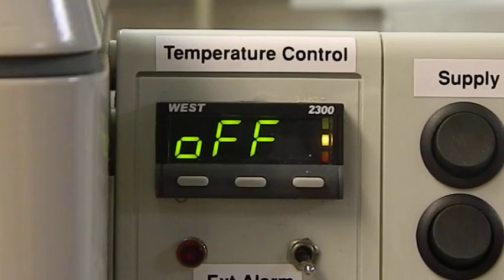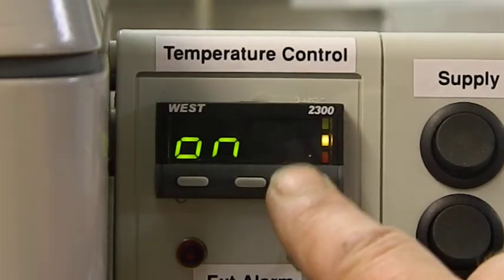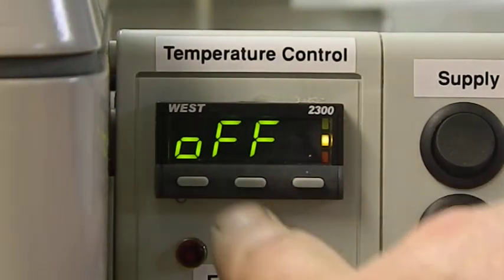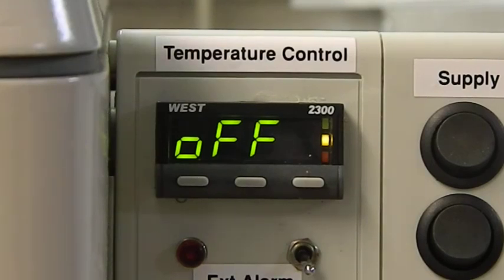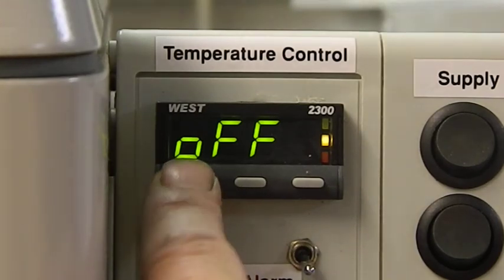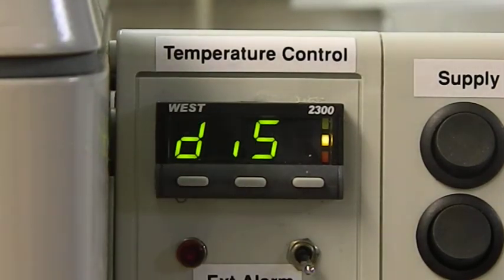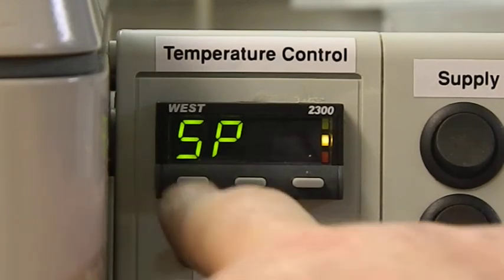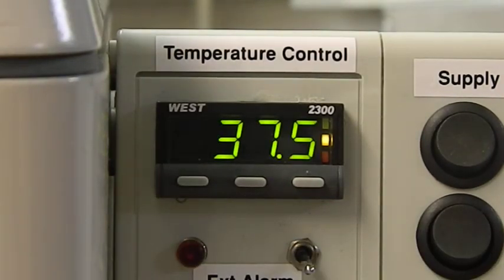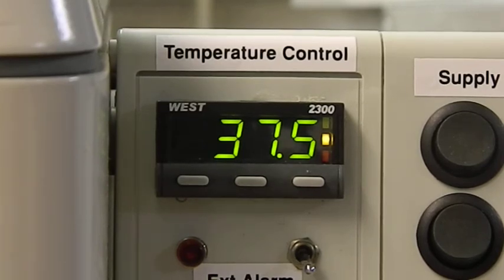SPL, this is a set point lock. If you don't want anyone to be able to change the settings you put in, you change this to on, and it'll lock out the buttons. So without going back into the parameters, it stops little fingers changing things. But again, we leave that off as a default setting. AEN, this is in disable mode at the moment. We don't use the parameter, so it's disabled. It'll take you back to SP 37.5. So we're back to where we started at the beginning of the second set of parameters.